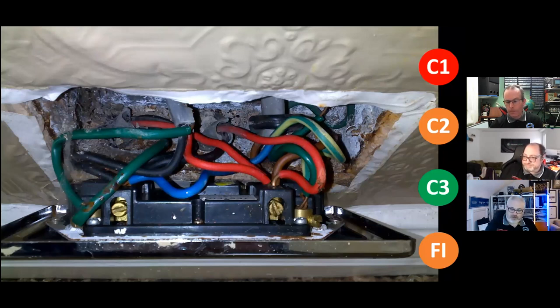So I'm also seeing, definitely, when that gets put back, massive strain placed upon the conductors. You can see even one of the neutrals there turning white where it's being pinched, just in the centre of the screen there. You can see the line conductor coming out to the top and the right. You see the right-hand line conductor, the red one? Yeah. The top of that has thinned a bit as it's been worn, probably brushing the ceiling of the socket as it's been pushed in there. You then got the old green sleeving as well for the CPC.